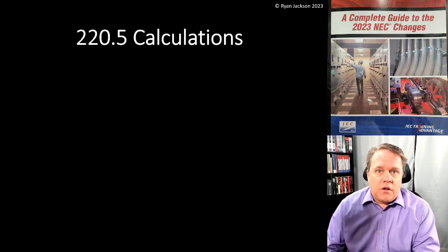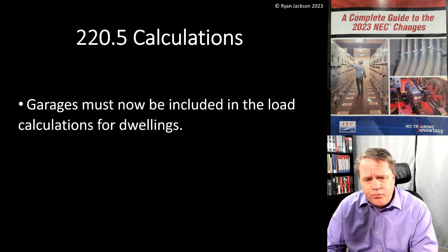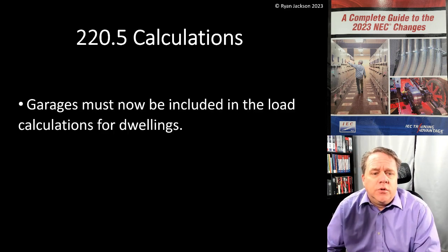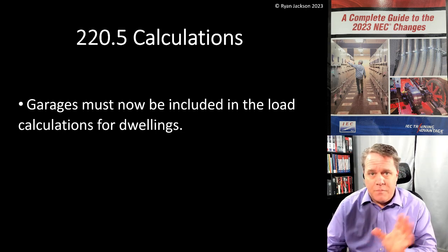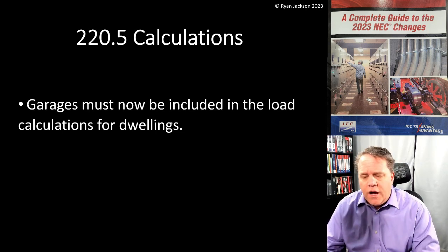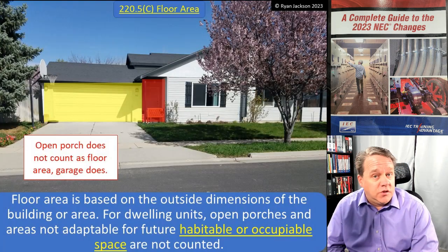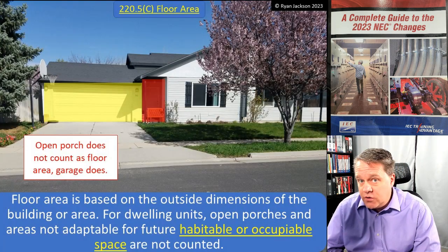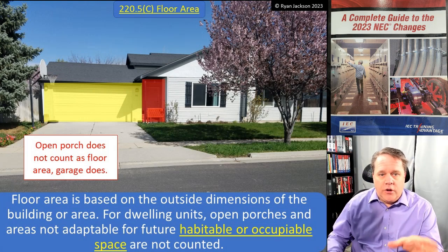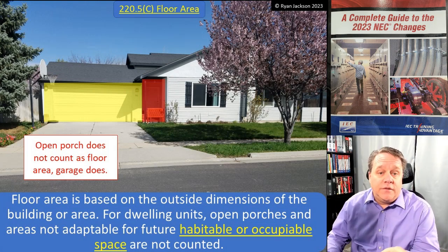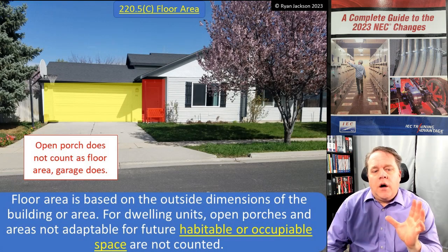Getting into the technical stuff: 220.5 — garages must now be included in the load calculation for dwellings. Now that's the way I phrase it, but you could argue that this change actually reduces the load calculation instead of increases it. When we're calculating floor area under 220.5(C) — this used to be in 220.11 — floor area is based on the outside dimensions of the building or area.